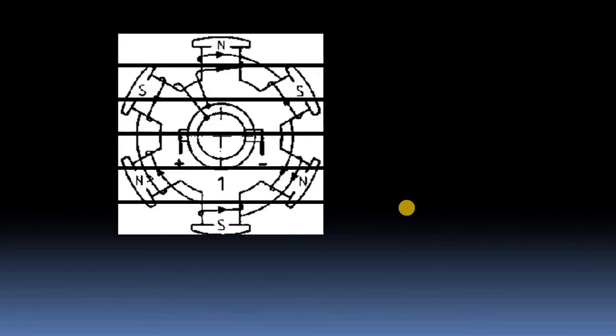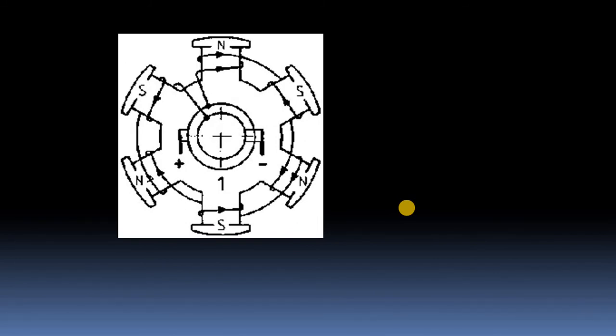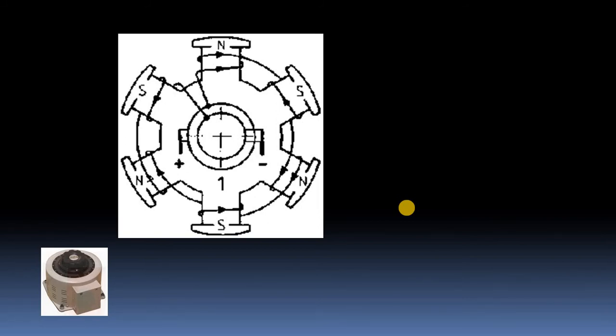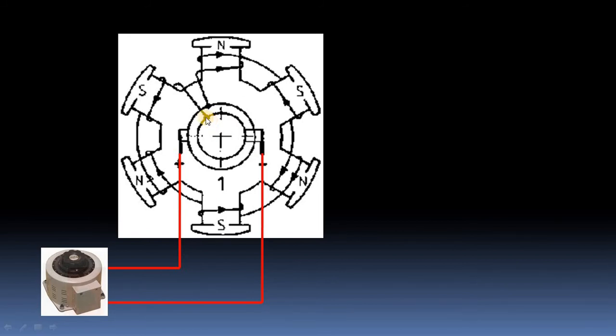Here I am assuming an alternator or synchronous motor having six poles. I apply the voltage using a dimmerstat or variac — a variable transformer where the input voltage is 230 volts and the output can be varied from 0 to 270 volts. I apply voltage to the slip rings: positive connected to phase, negative to neutral. From the slip rings the rotor winding connects pole one through pole two, three, four, five, and six — all six poles are connected in series.